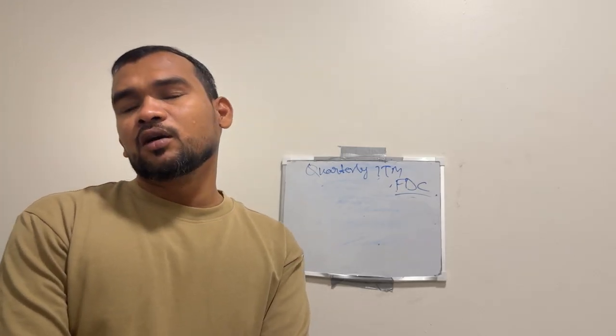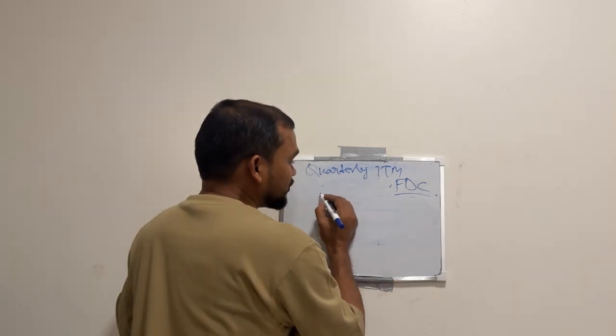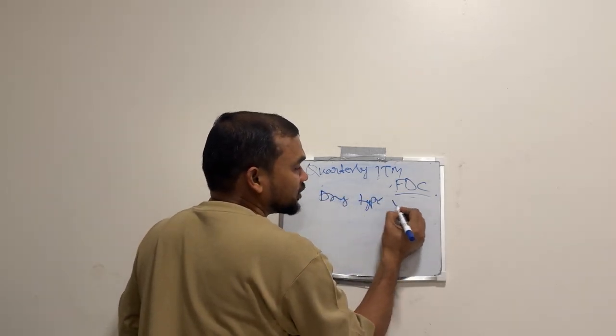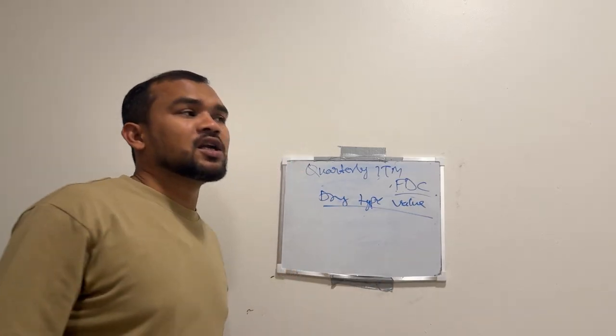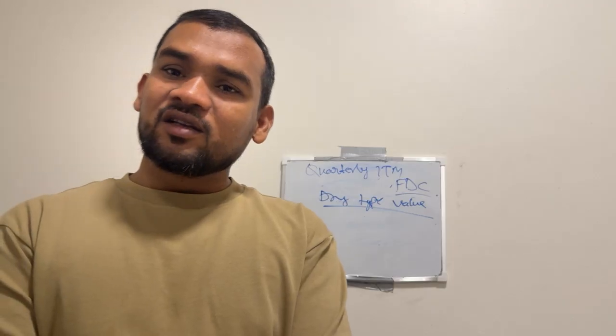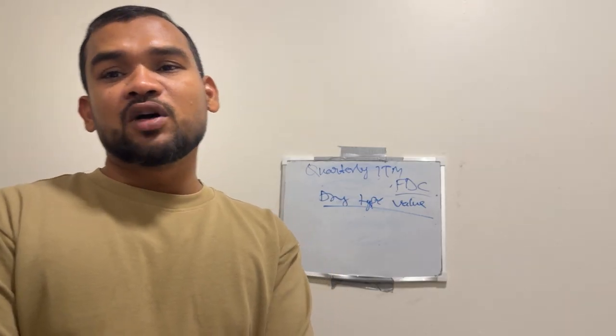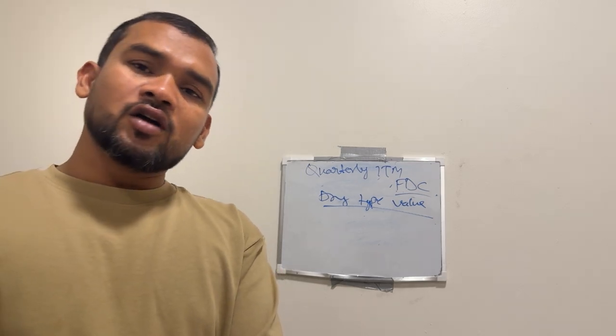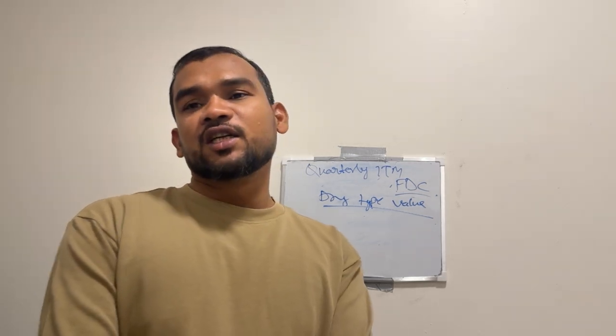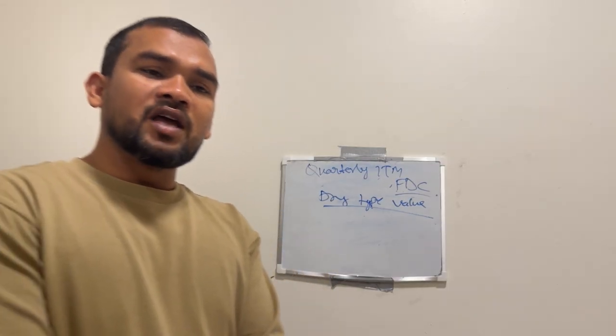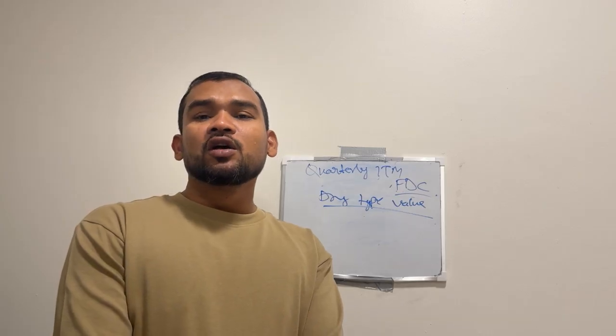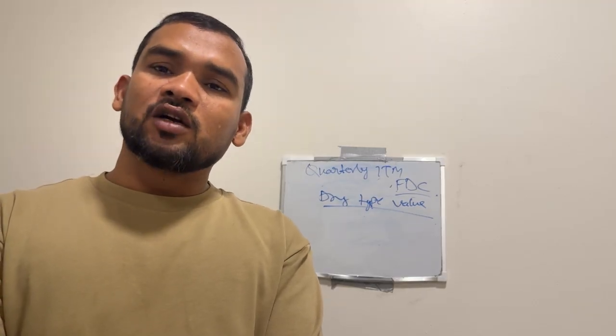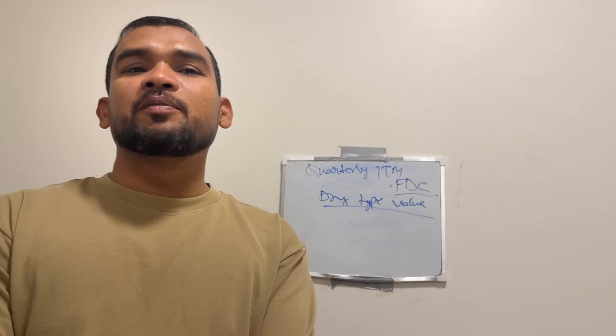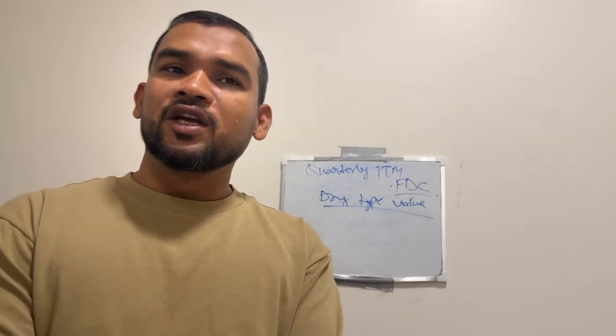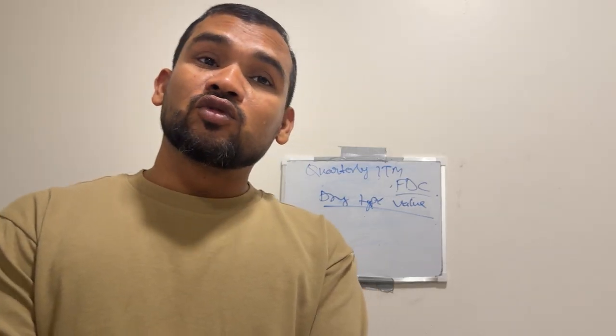We have another topic, quarterly inspection for dry pipe valve. In a dry pipe valve we have air and we have water, before and after the dry pipe valve. So we do the inspection on a quarterly basis, and we also test the system quarterly for this dry pipe valve. In the quarterly inspection we check the minimum requirements: the priming water level is tested on a quarterly basis, and we also check the dry pipe valve associated components like trim, quick opening device, and the main drain, which we have to test quarterly.